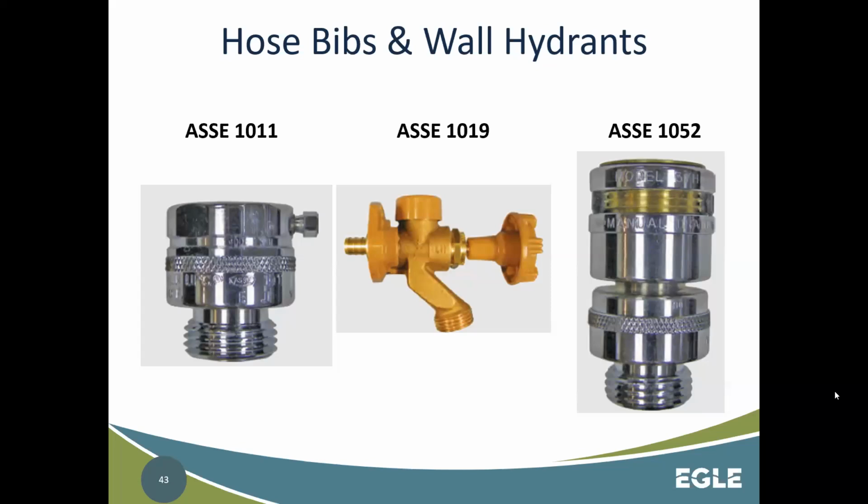Again, with all of these being atmospheric vacuum breakers, they should not have any downstream valves. They cannot be subject to continuous pressure. So that's stuff when it comes to maybe explaining to the homeowner or business owner, wherever these need to be added on, that if you leave a hose connected on it with, again, a splitter further down, or one of your spray nozzles or something, that is potentially defeating the purpose and might make these malfunction.